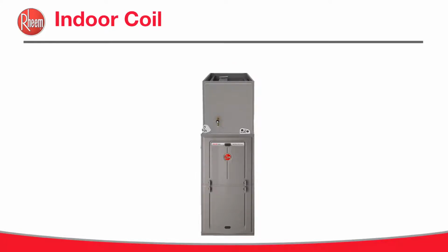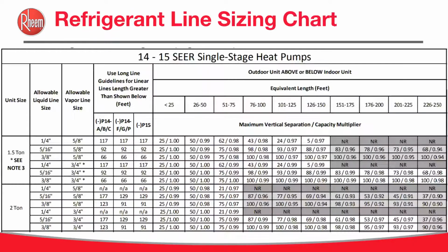Now let's look at refrigerant line sizing. But before we begin, we need to know why line sizing is so critical and the purpose of the suction and liquid line. So the liquid line is to transport a warm, subcooled liquid to the metering device. In cooling mode, the metering device is located indoors. And in heating mode, the metering device is located outdoors. So this is one of the differences from a heat pump to an air conditioner. With an air conditioner, you're only going to have a metering device indoors. You're not going to have one in the outdoor unit.